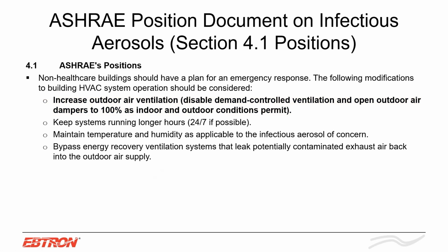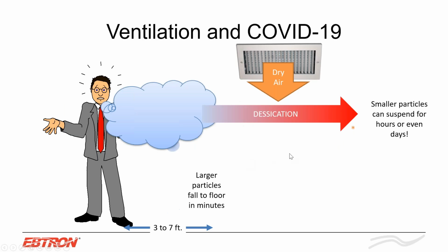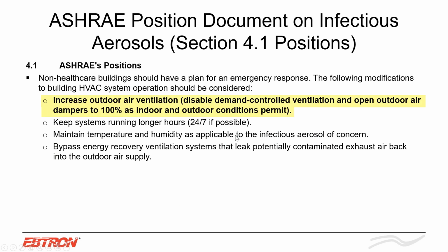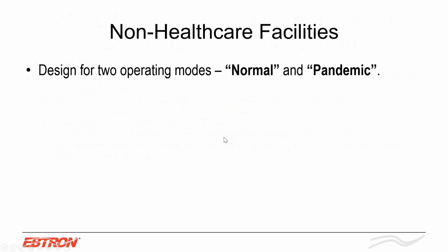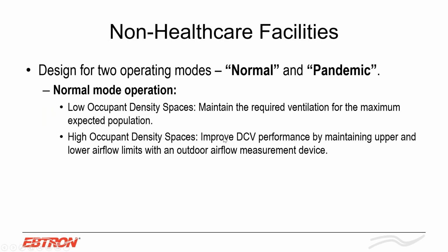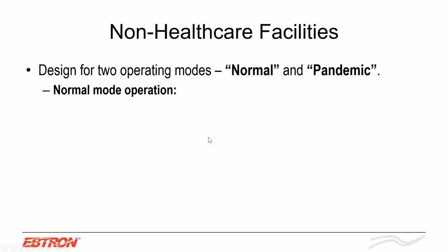There's been studies that have shown that maintaining a humidity at 40 to 60% is optimal for infectious aerosols, and that kind of goes back to this, right? If you have dry air, those particles can be suspended in the air for longer. So, what are certain design engineers doing to try to provide a solution to this?